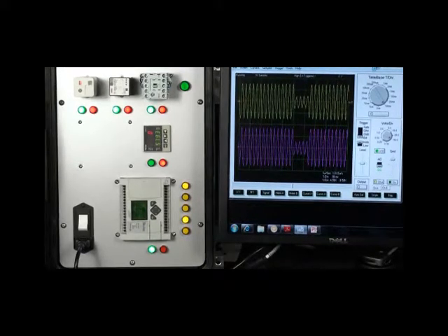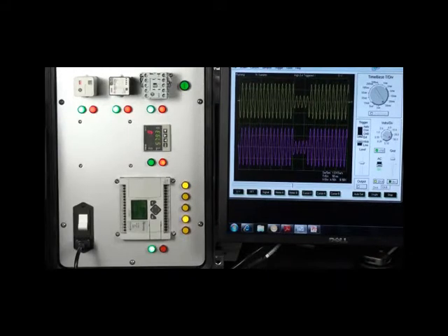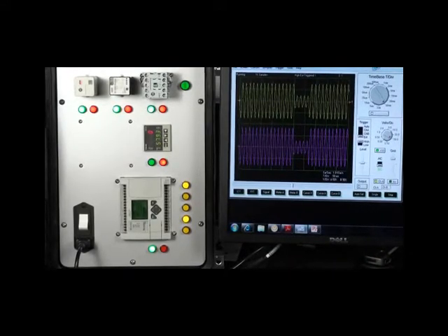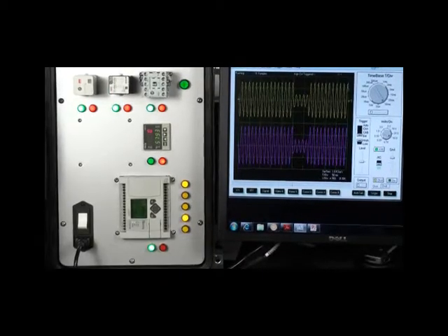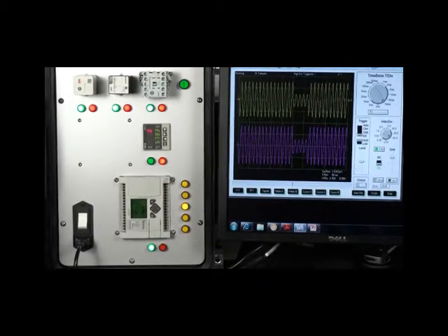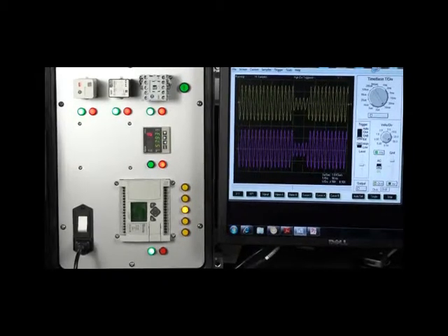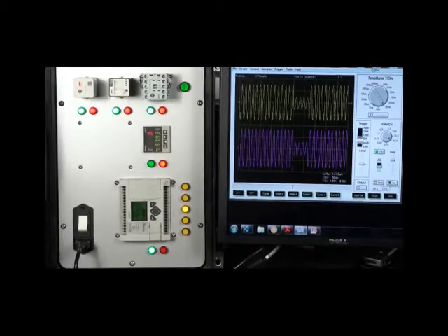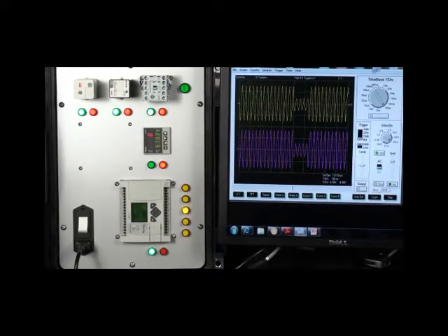Here we've lost the contactor, the relay, the counter, as well as the DC power supply. What you might notice here is that the PLC is still running. Typically, the PLC is the most rugged component in the entire cabinet. It's everything that's hooked to it that's at risk of dropping out from this type of sag. Again, would the lights have blinked? I'm not sure. It's only about 4 cycles long. So it probably won't be attributed to a power sag.